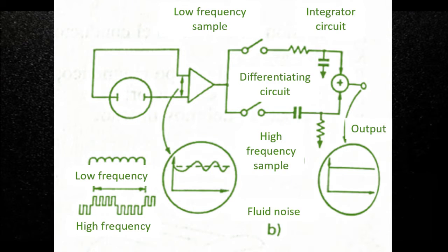They are less sensitive to electrode coating problems, but their response is slower, which is unacceptable for certain types of control. Other manufacturers feed the magnetic field coil with two superimposed waves, one of low frequency, which gives a very good zero stability, and one of high frequency, that is immune to the noise generated by the high viscosity of the liquid, electrochemical reactions, and/or low conductivity.